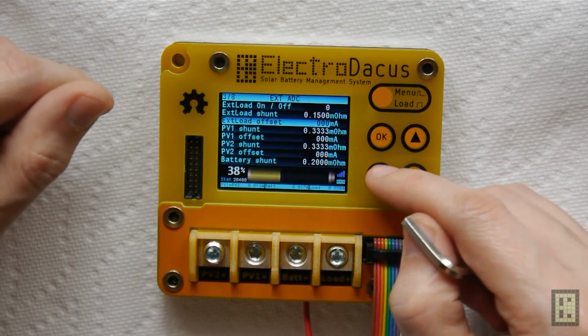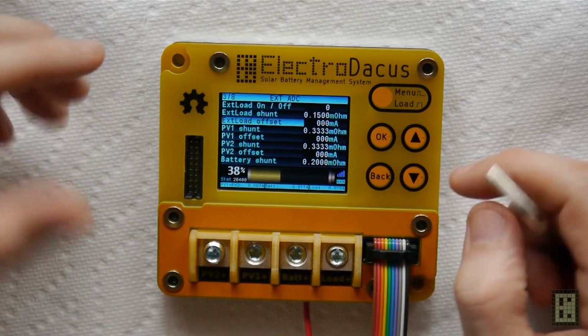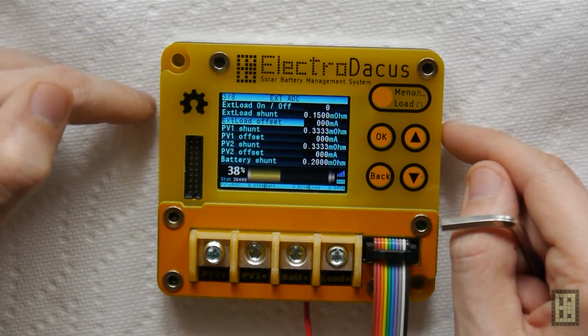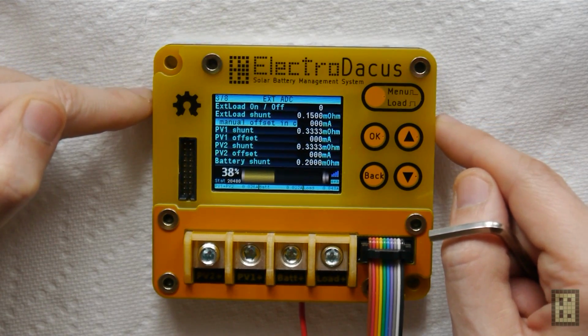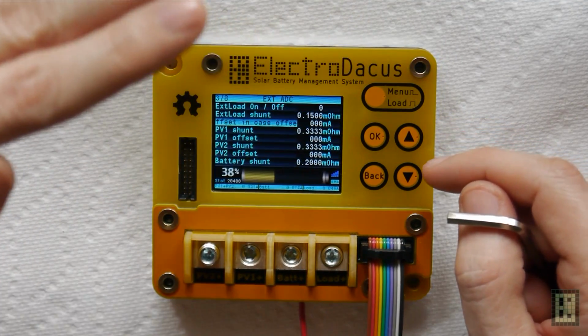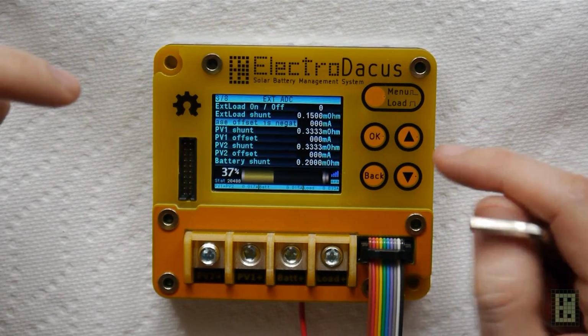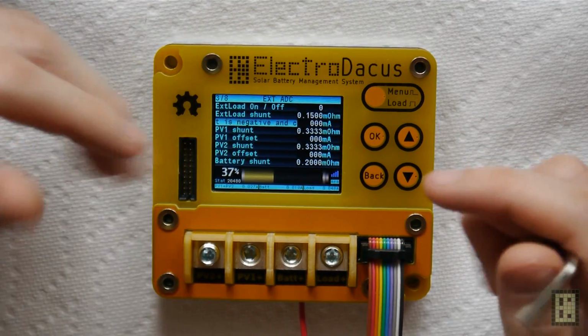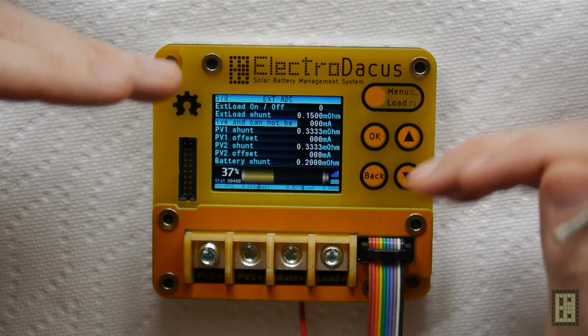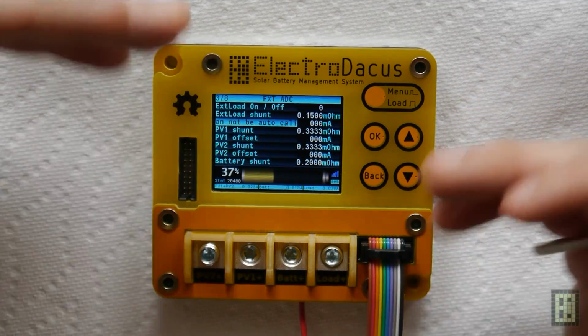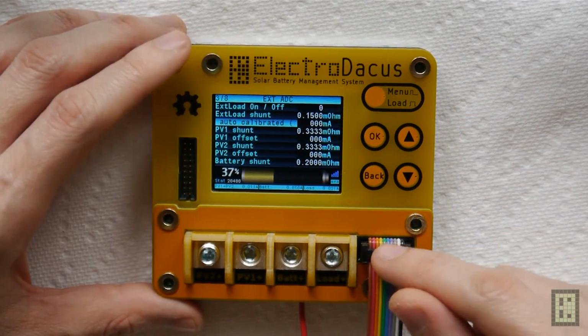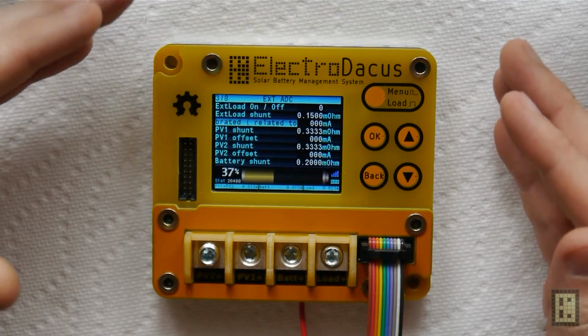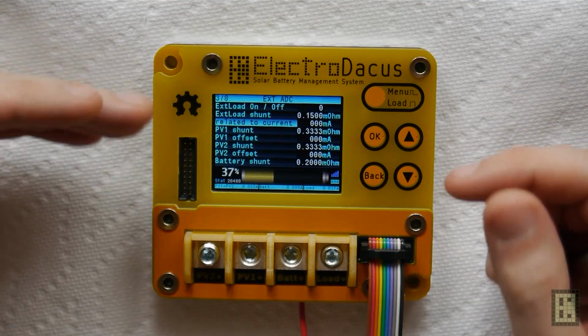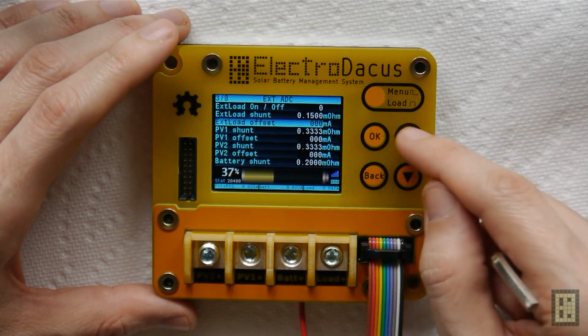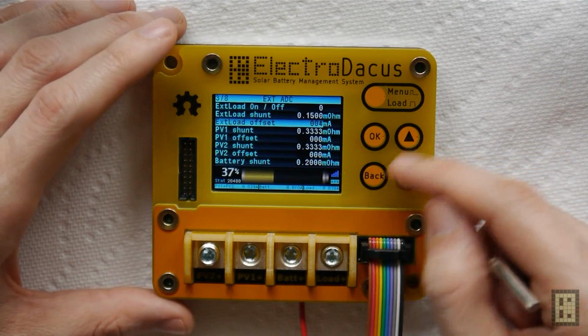In case there is any offset, you can manually adjust the offset of the external current shunt reading. There are current sense amplifiers here that can have a positive or negative offset. If the offset is positive, the ADC can see that and it will auto calibrate when you power the solar BMS on and off. But if the offset is negative, you need to add that offset manually.